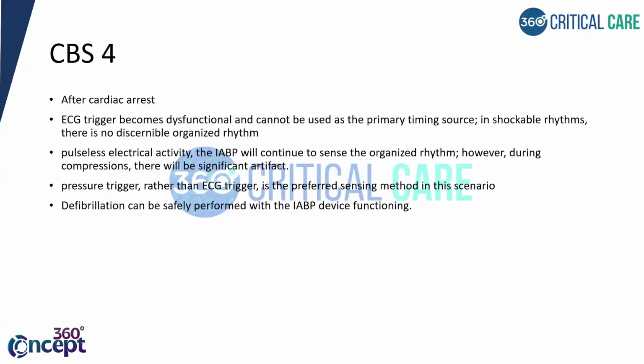You can put it to arterial mode, or you can put it to the auto mode. So one of them you can try. In pulseless electrical activity, the IABP will continue to sense the organized rhythm. During compressions, there will be a significant artifact, so it may not be very effective. So pressure trigger, rather than ECG trigger, is the preferred sensing method.